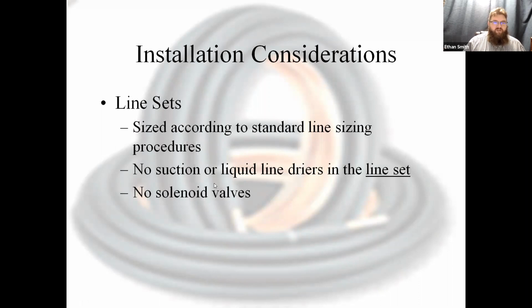We don't use solenoid valves anymore, guys. Make sure your solenoid valves are gone. All the coils, both indoor and outdoor these days, are integrally trapped. So we don't need solenoid valves to prevent migration in heat pump systems.